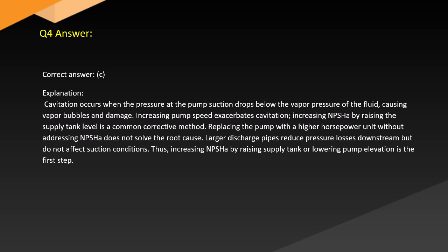Answer. Correct answer, C. Explanation. Cavitation occurs when the pressure at the pump suction drops below the vapor pressure of the fluid, causing vapor bubbles and damage. Increasing pump speed exacerbates cavitation. Increasing pressure by raising the supply tank level is a common corrective method.